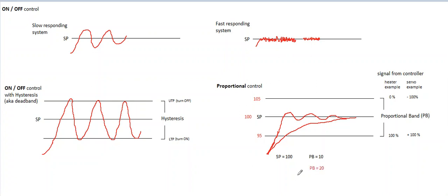In this example, you would call this a different tuning. Notice I increased the proportional band maybe to something like 20. If you can picture, the proportional band was from here to here, and I sort of said, let's start decelerating sooner so that we don't overshoot. So the proportional band, conceivably, I might have changed that to 20, 110 and 90, it'd be 20 degrees.